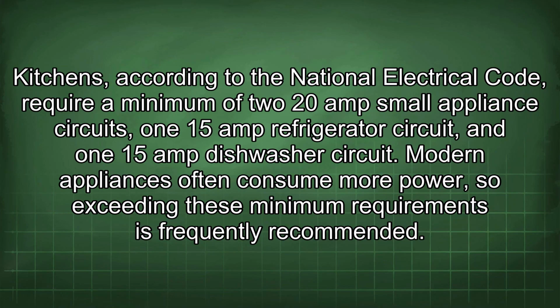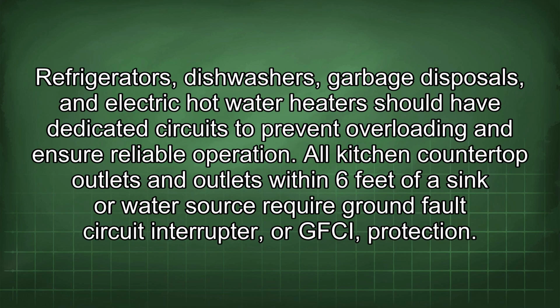Kitchens, according to the National Electrical Code, require a minimum of two 20-amp small appliance circuits, one 15-amp refrigerator circuit, and one 15-amp dishwasher circuit. Modern appliances often consume more power, so exceeding these minimum requirements is frequently recommended. Refrigerators, dishwashers, garbage disposals, and electric hot water heaters should have dedicated circuits to prevent overloading and ensure reliable operation.